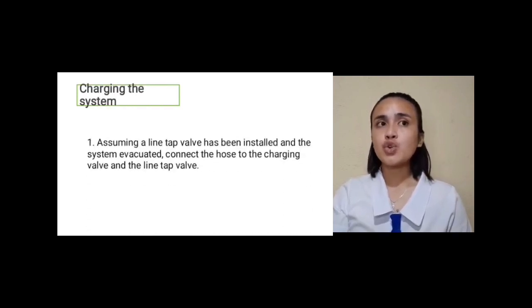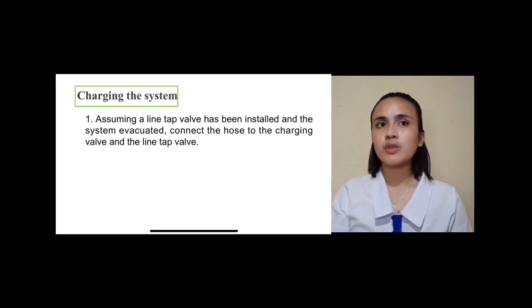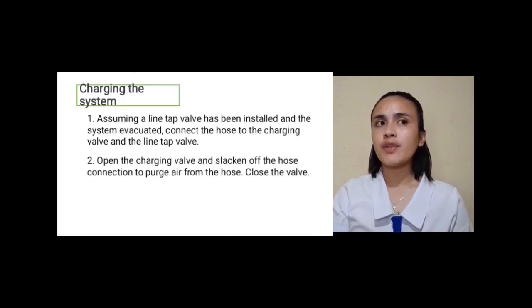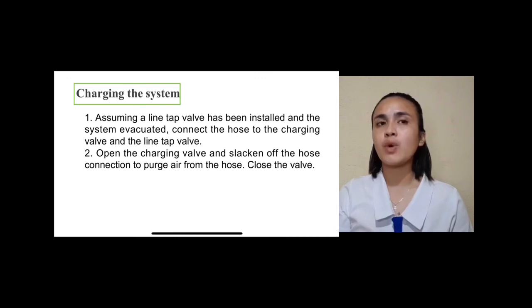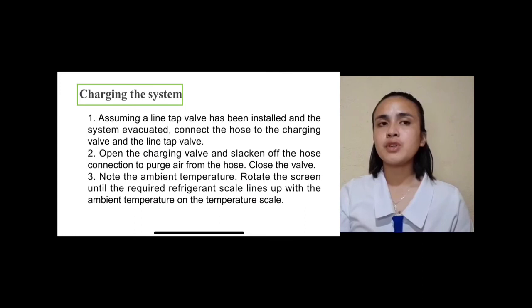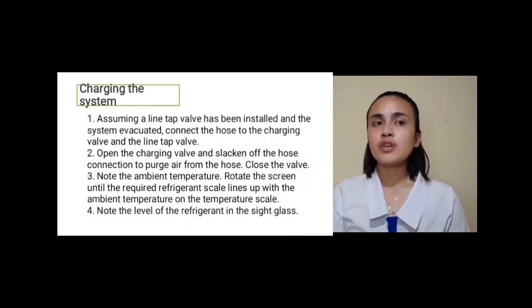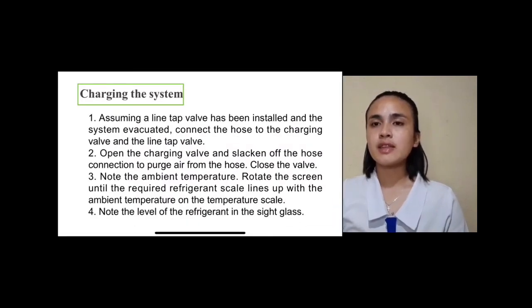Number 1. Assuming a line tap valve has been installed and the system evacuated, connect the hose to the charging valve and the line tap valve. Number 2. Open the charging valve and slacken off the hose connection to purge air from the hose. Close the valve. Number 3. Note the ambient temperature. Rotate the screen until the required refrigerant scale lines up with the ambient temperature on the temperature scale.